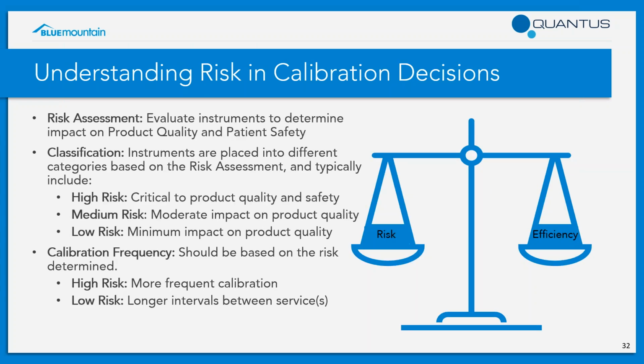So we talked a lot about risk in the presentation so far, and I wanted to provide some typical areas of risk within your program. The first one, which we've talked about the most, is your risk assessment. Instruments and equipment are evaluated to determine their impact on product quality and patient safety. This assessment considers factors such as the instrument's role in the manufacturing process, the criticality of the measurement it provides, and the potential consequences if there are inaccurate measurements.